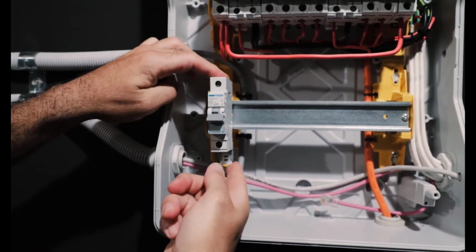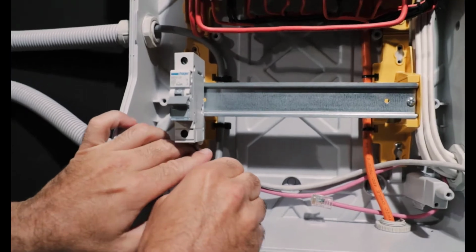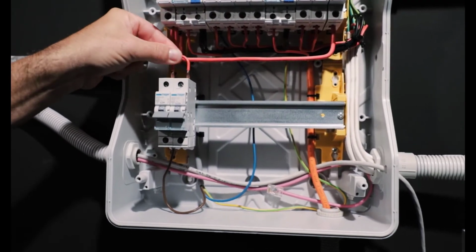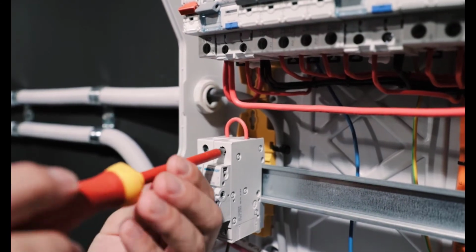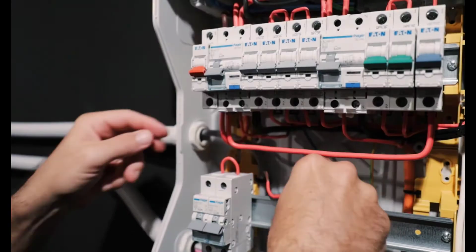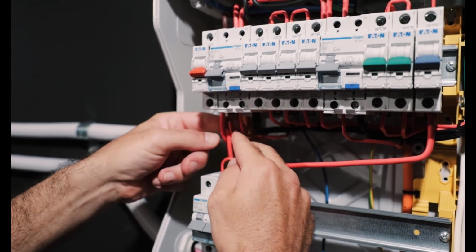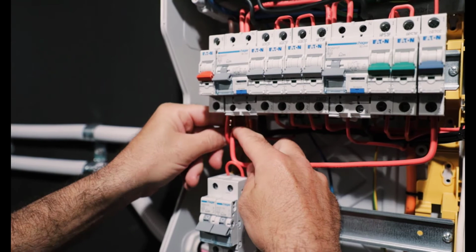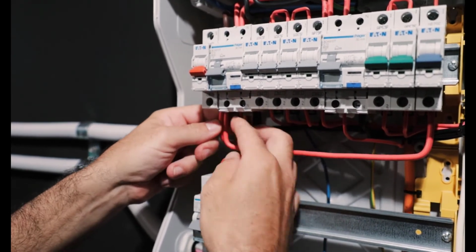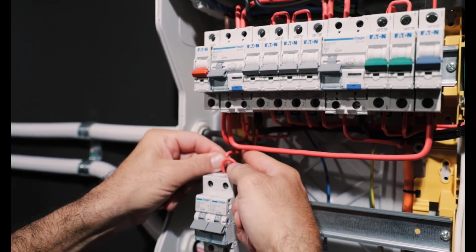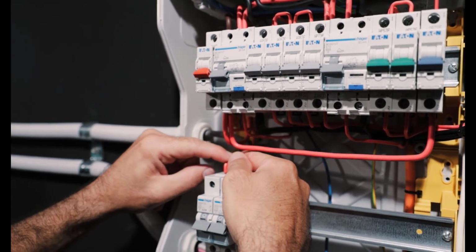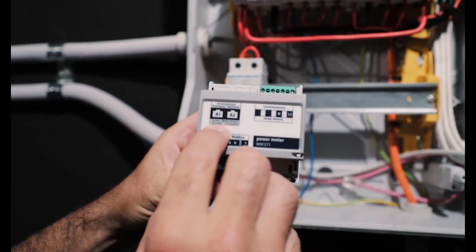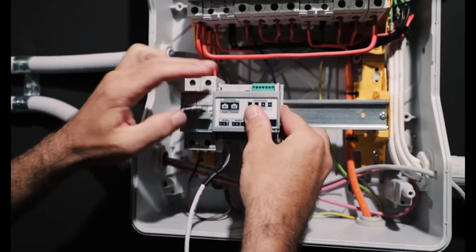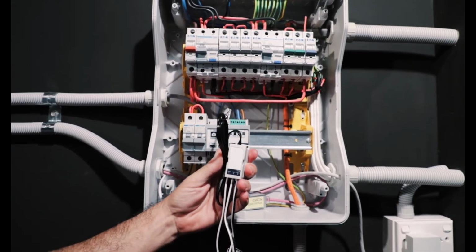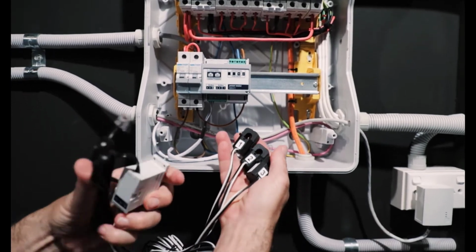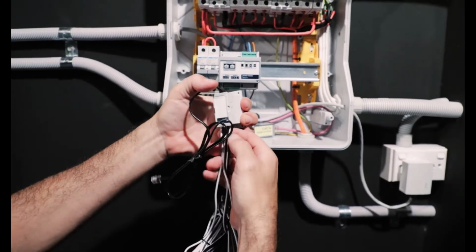So once again, we get the AC isolator in place from the Sonnen system, and then we take the supply from the Sonnen, or the active going from the Sonnen MCB through to the combined AC from the main isolator. The meter goes in again. Now bring our CT sets in once more. So transducer goes on.